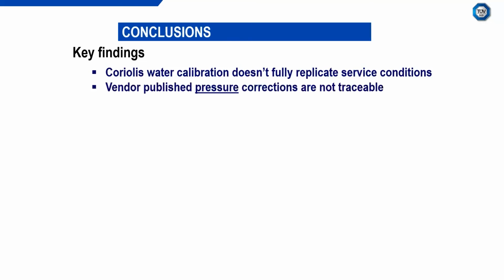Next point is that the vendor published pressure corrections are not traceable. Not all manufacturers publish a pressure correction, and even the ones that do, not all the pressure corrections are traceable. So you can't just rely on the manufacturer data sheet. Temperature affects a magnitude less than pressure, and that's not due to the physics, that's more due to the fact that it's compensated for directly. Coriolis meters have an RTD to measure the temperature and correct for it. They do not ship with a pressure probe to correct for pressure. So you have to either apply a constant correction, apply no correction, which a lot of people are unwittingly doing, or apply a dynamic correction with a pressure transmitter into the flow computer or into the software of the Coriolis meter.